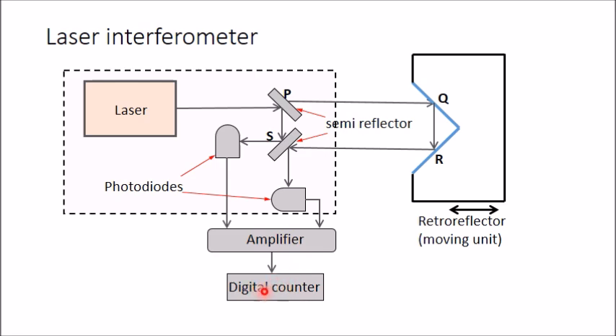This digital counter counts the number of dark and light bands during the movement of the retro-reflector. It is calibrated to convert this into the distance traveled by the retro-reflector. In this way, whatever distance is traveled by this retro-reflector mounted on a slide will be determined through this digital counter.